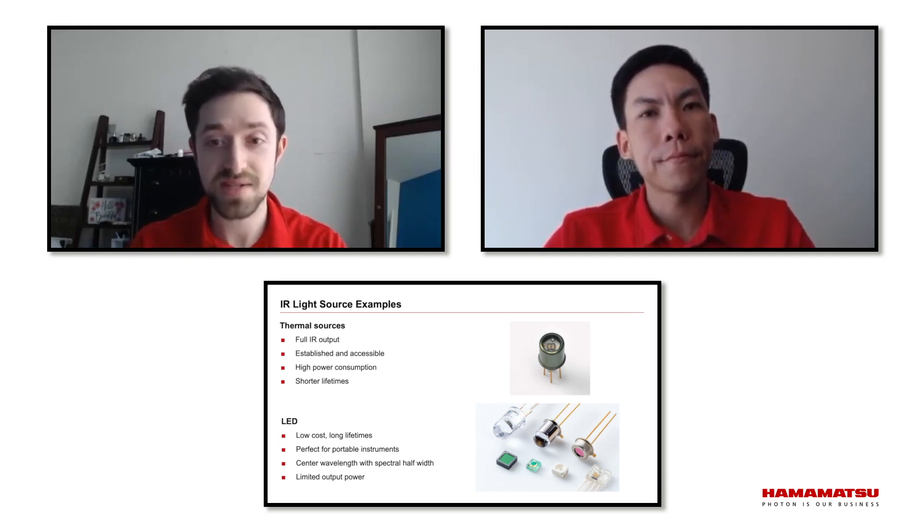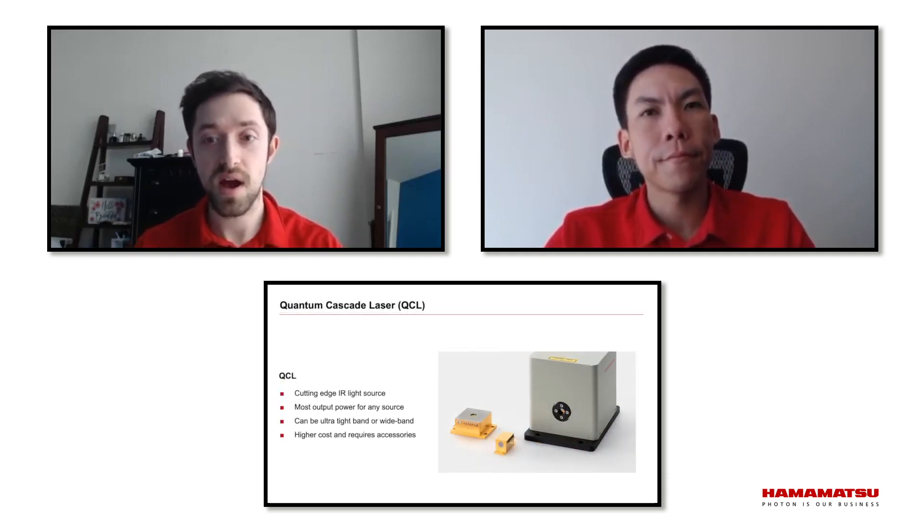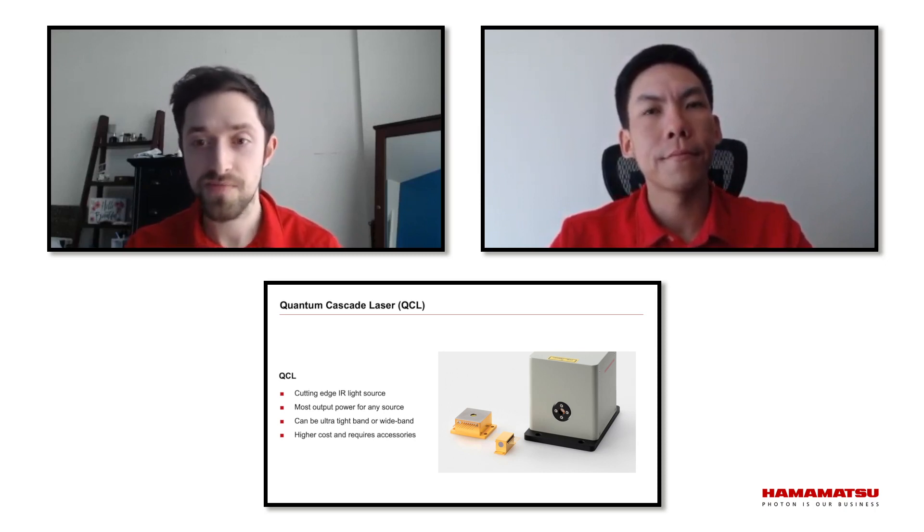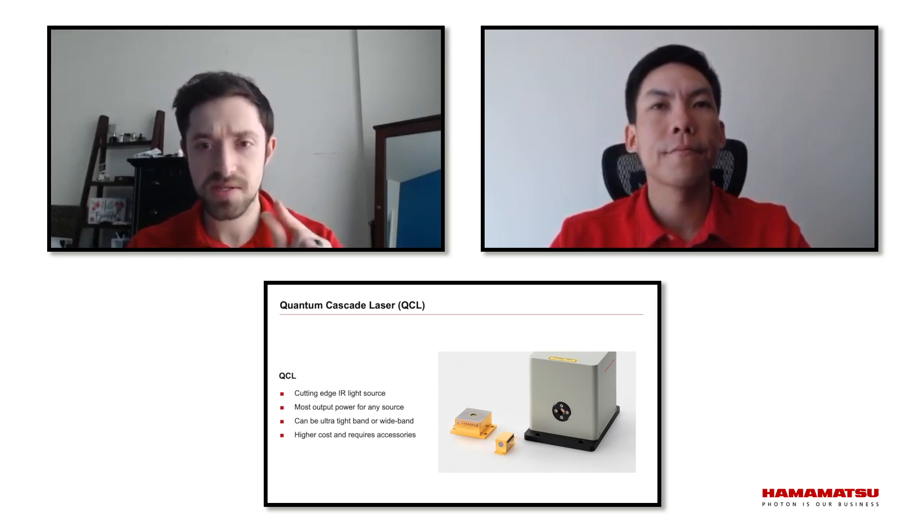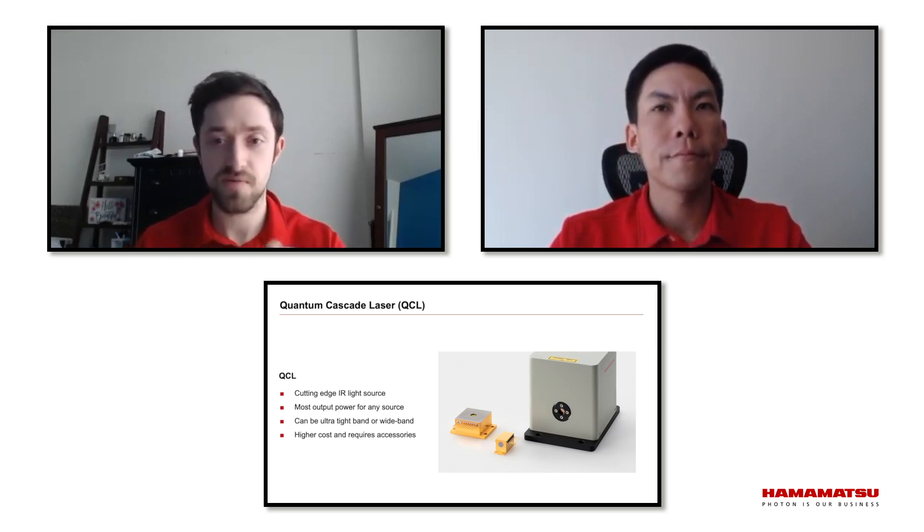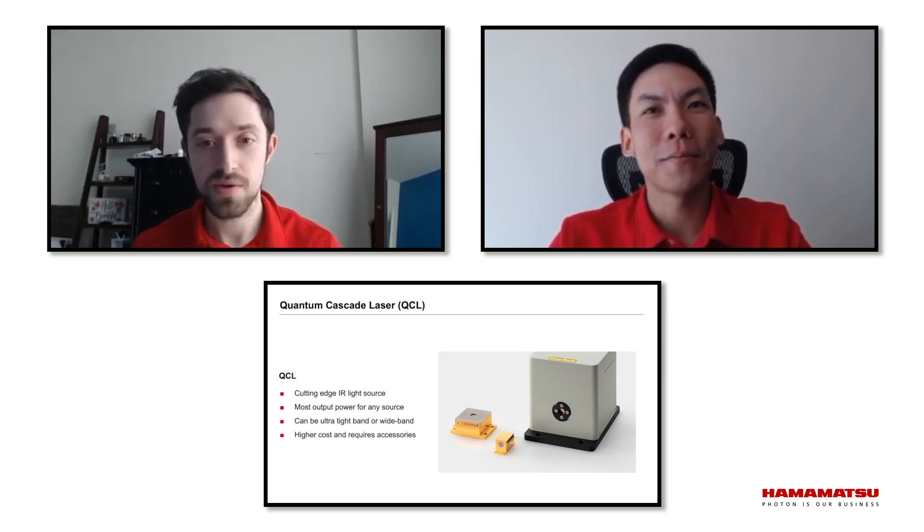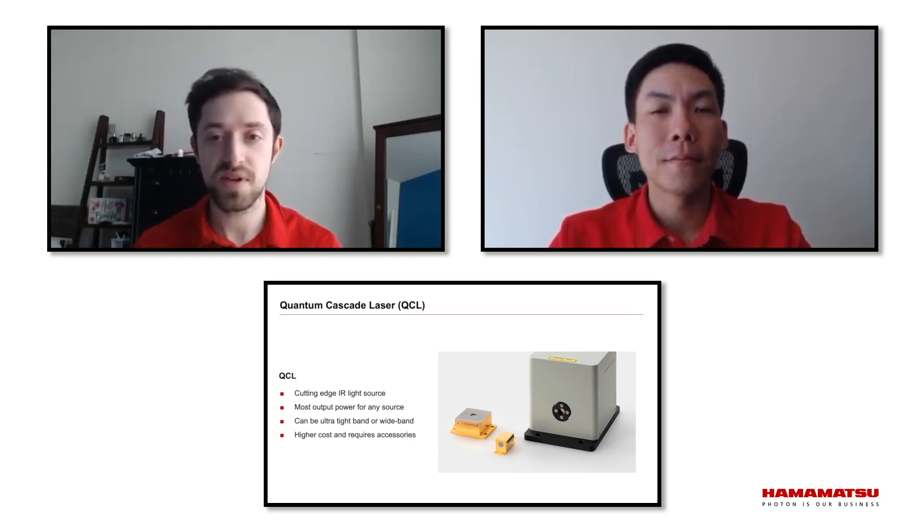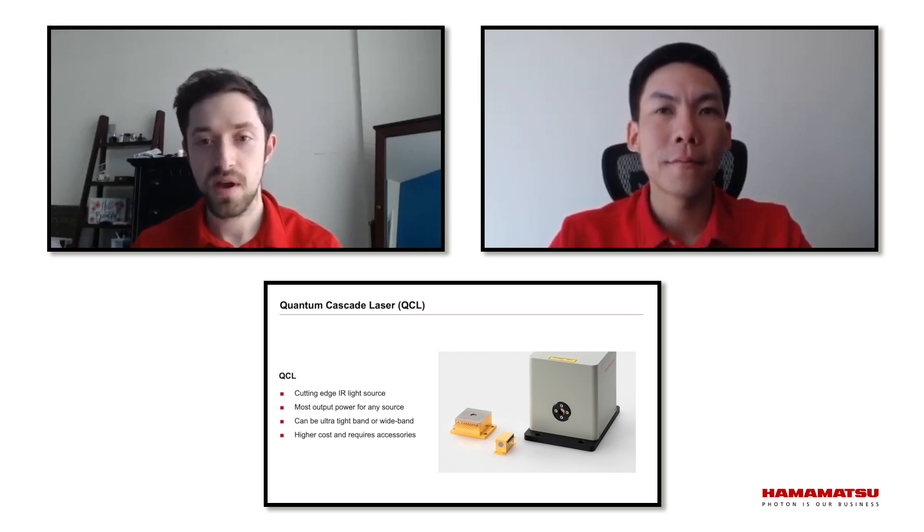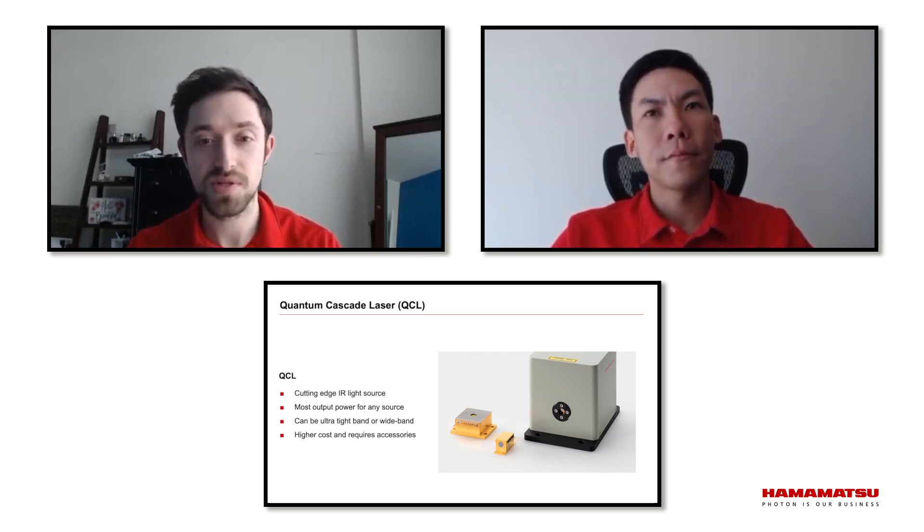Then there's the quantum cascade laser. This is the highest echelon of infrared light sources. It will provide the most output, can provide very specific bands, which is great for gas analysis or very wide band with high output. Everyone wants more output. Quantum cascade lasers are a very high performance component, usually pretty expensive. Again, I'll be expanding upon this later. So, when we take the example of light source, something in the middle, and detector, a classic example is moisture monitoring, something you run into a lot, right, Albert?